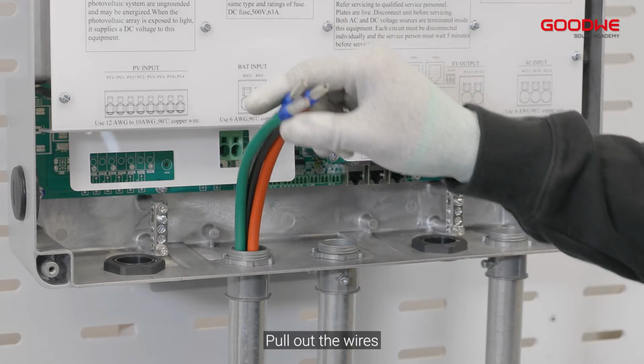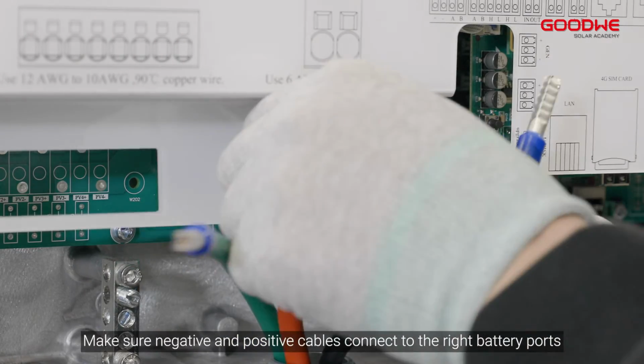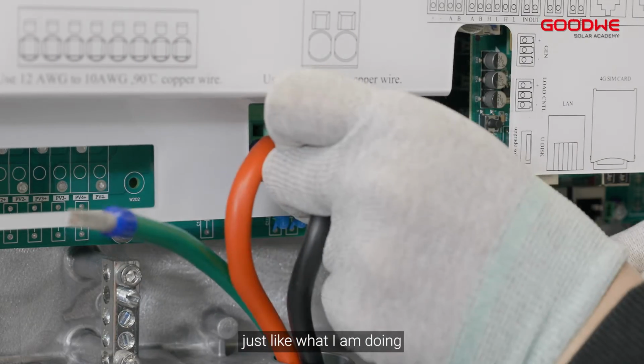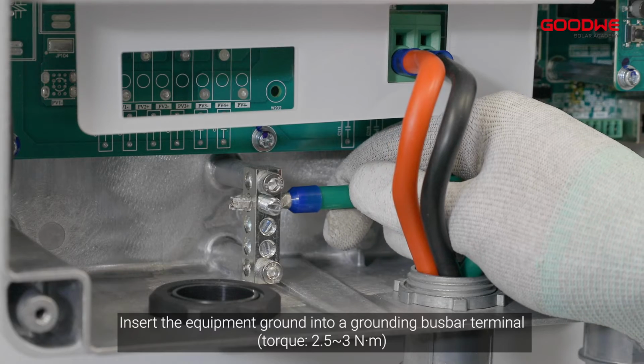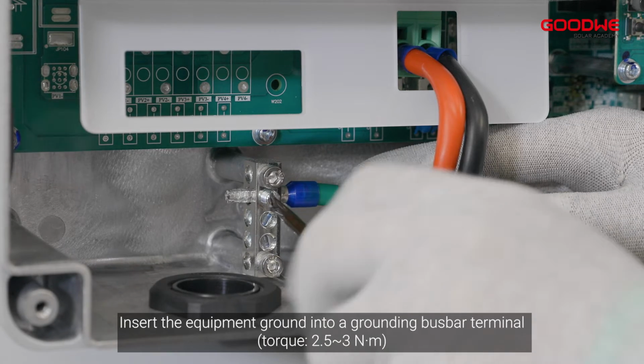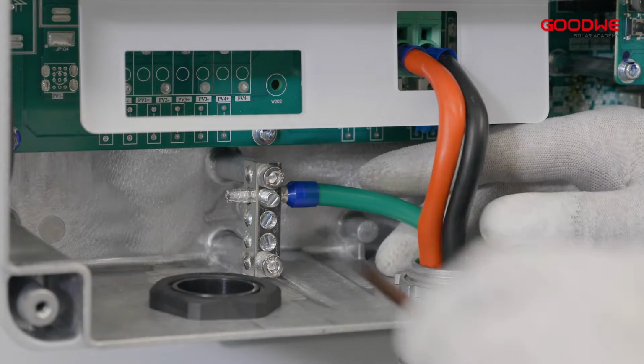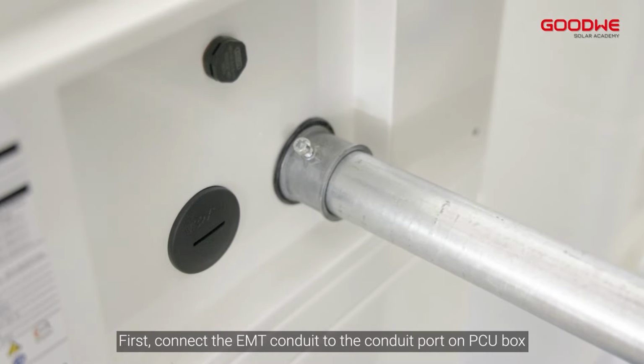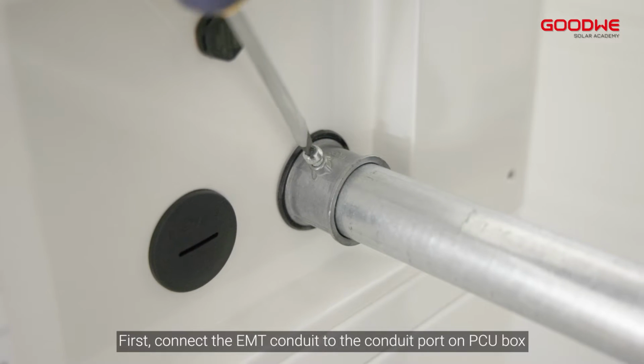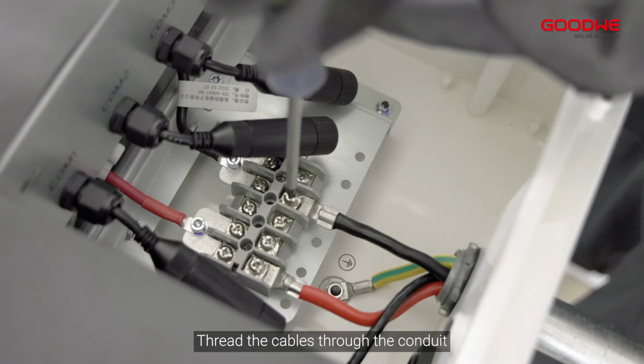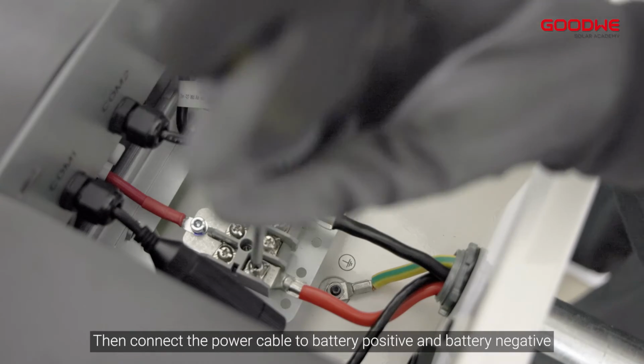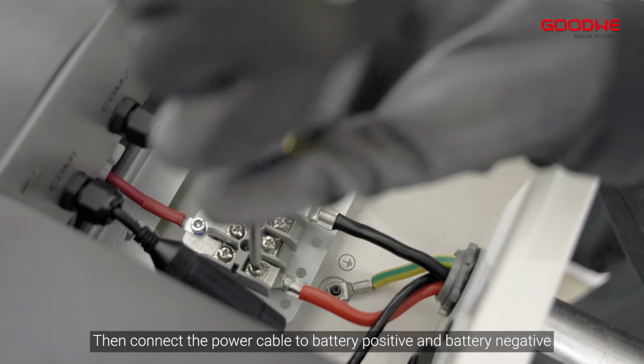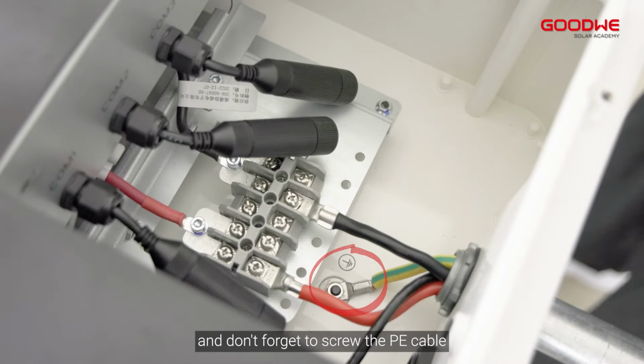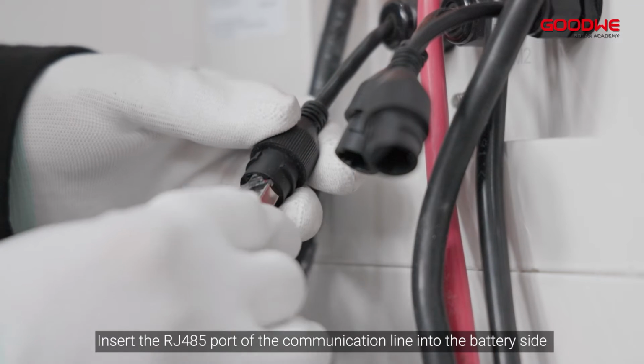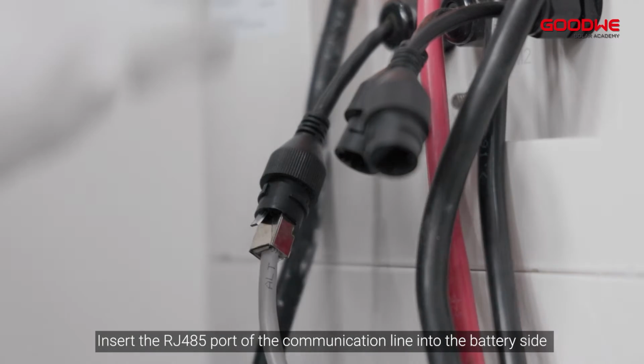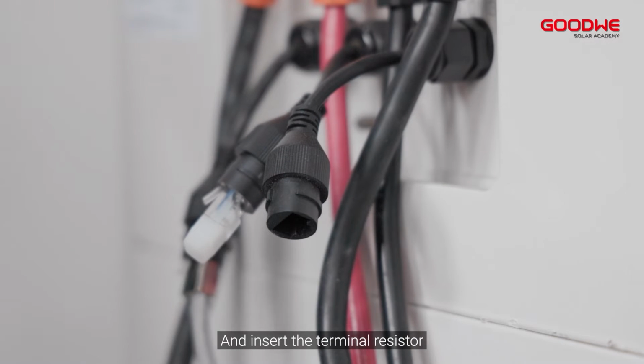Pull out the wires. Make sure negative and positive cables connect to the right battery ports, just like what I am doing. Insert the equipment ground into a grounding busbar terminal. First, connect the EMT conduit to the conduit port on the PCU box. Thread the cables through the conduit. Then connect the power cables to battery positive and battery negative. And don't forget to screw the PE cable. Insert the RS485 port of the communication line into the battery side, and insert the terminal resistor.